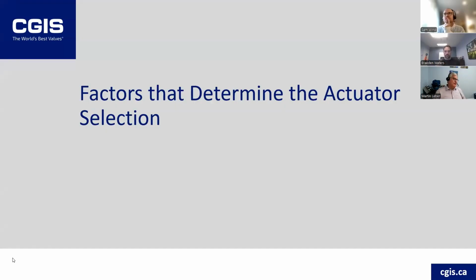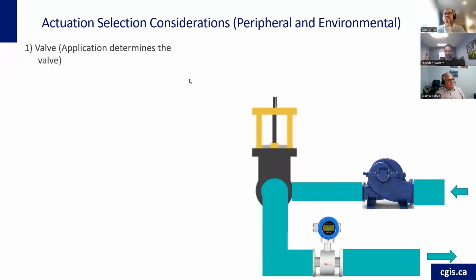The next topic we want to cover is factors that determine the actuator selection. We're now looking at the actuator peripheral and environmental considerations. So always the application determines the valve. The actuator is always secondary to selecting the valve. You won't select an actuator and then put a valve on it. It's always the other way around. So it's critical to get this right, because it impacts the type of automation that you will be requiring.